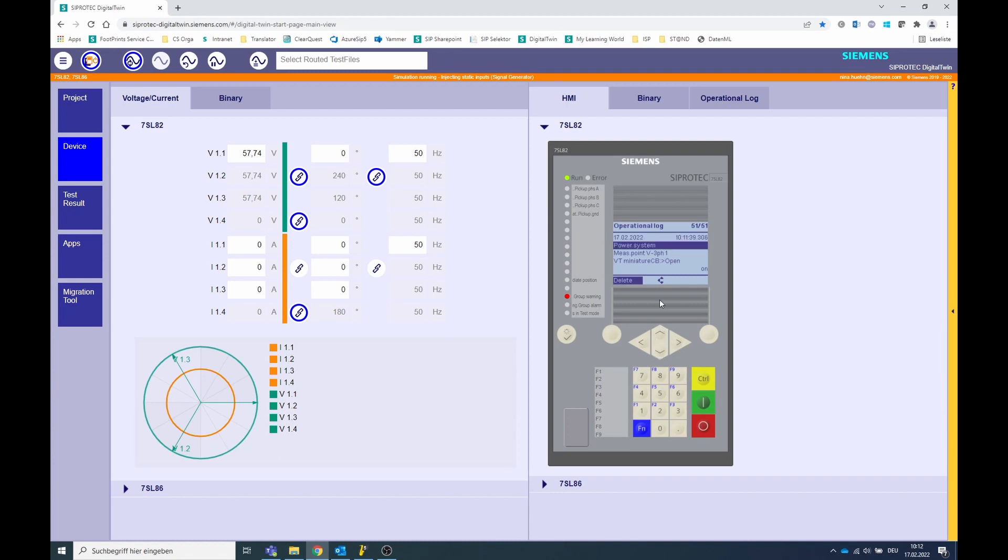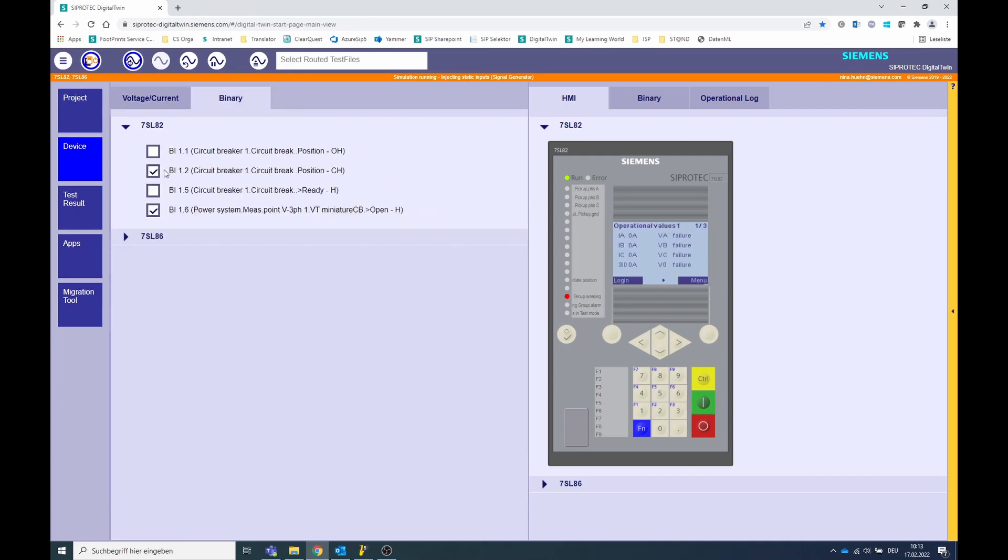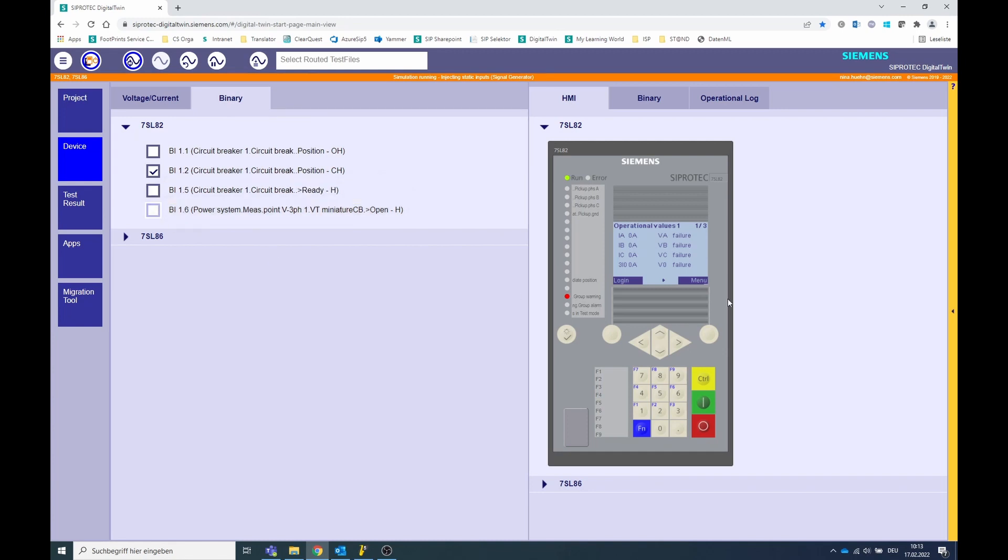Here you should find the information that the voltage transformer circuit breaker is reported as on. If this is the case, check whether the actual position signal of the voltage transformer circuit breaker matches the parameterization in the DIGSI information routing.